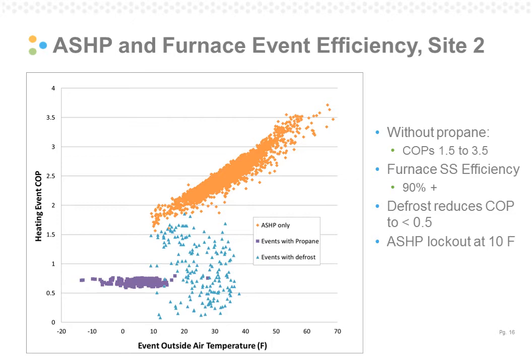On this slide, we're going to look at heating events. So the previous slide was daily average system efficiency. On this slide, we're looking at heating event efficiency. So on the y-axis, you have the heating event coefficient of performance, and on the x-axis, you have the heating event outside air temperature in Fahrenheit. And this data is only for site 2. At this site, we had a condensing furnace with a steady state efficiency of above 90%.